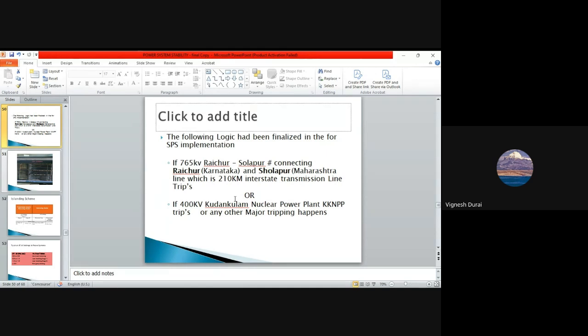frequency is balanced. Okay. Again, our Kudankulam nuclear power plant is 2000 megawatts. If 2000 megawatts immediately goes out of the grid, again we will face some unbalance in the system, so we have to give relief to the system immediately. So we will trigger some trips, so that we get relief from the network. Okay. So you can see the SPS scheme, Raichur Solapur trip signal 1. It means that we have certain feeders within this. Whenever this Raichur Solapur transmission line trips, these following feeders will be tripped immediately, so that it will give immediate relief to the grid. Okay. Apart from this, we have islanding schemes.